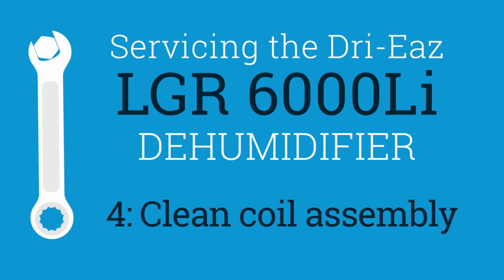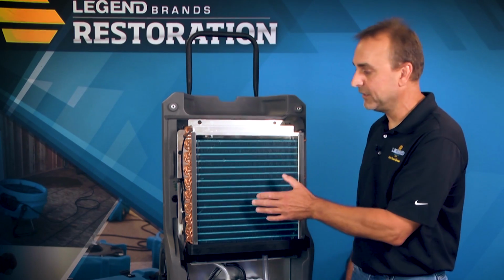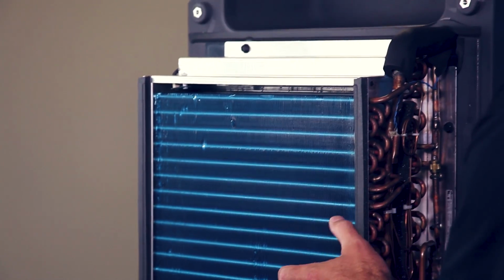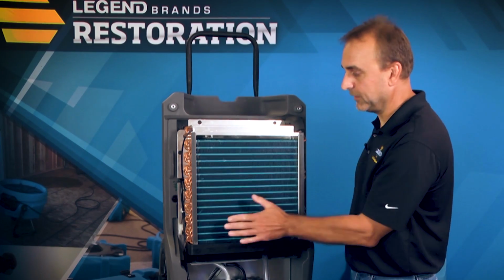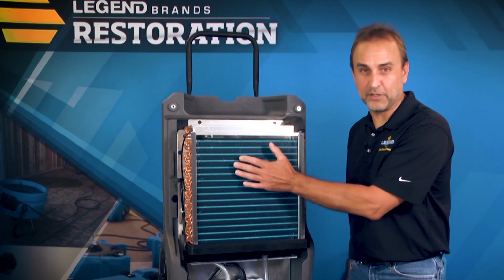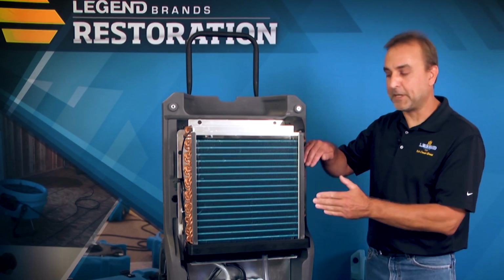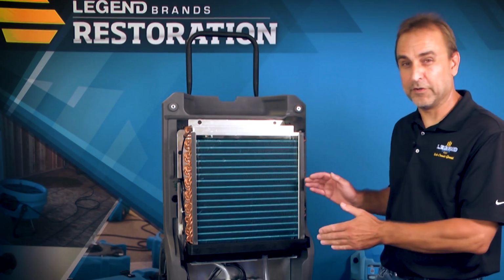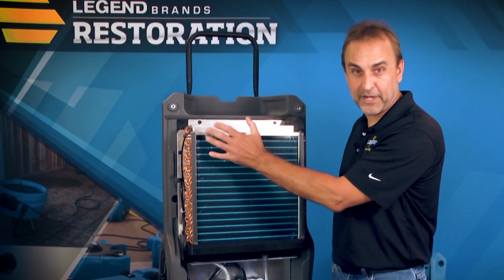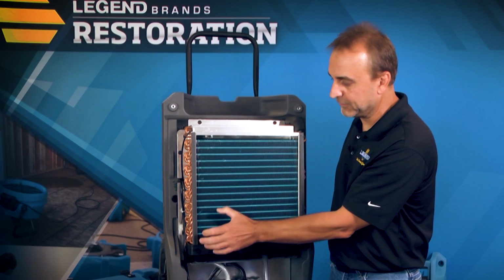When inspecting the coil assembly, you'll notice the coil has a blue coating. The coating adds to the efficiency, and as debris builds up on the coil, the first step is to vacuum the coil assembly from any debris. That counterflow will help pull it through. If you blow compressed air into the coil assembly, you'll just be blowing debris back into the unit, and we want to avoid that. So with a HEPA vac and a soft bristle brush, you don't want to poke the brush into the fin pack, but it'll allow you to get better airflow as the bristles get near the front.